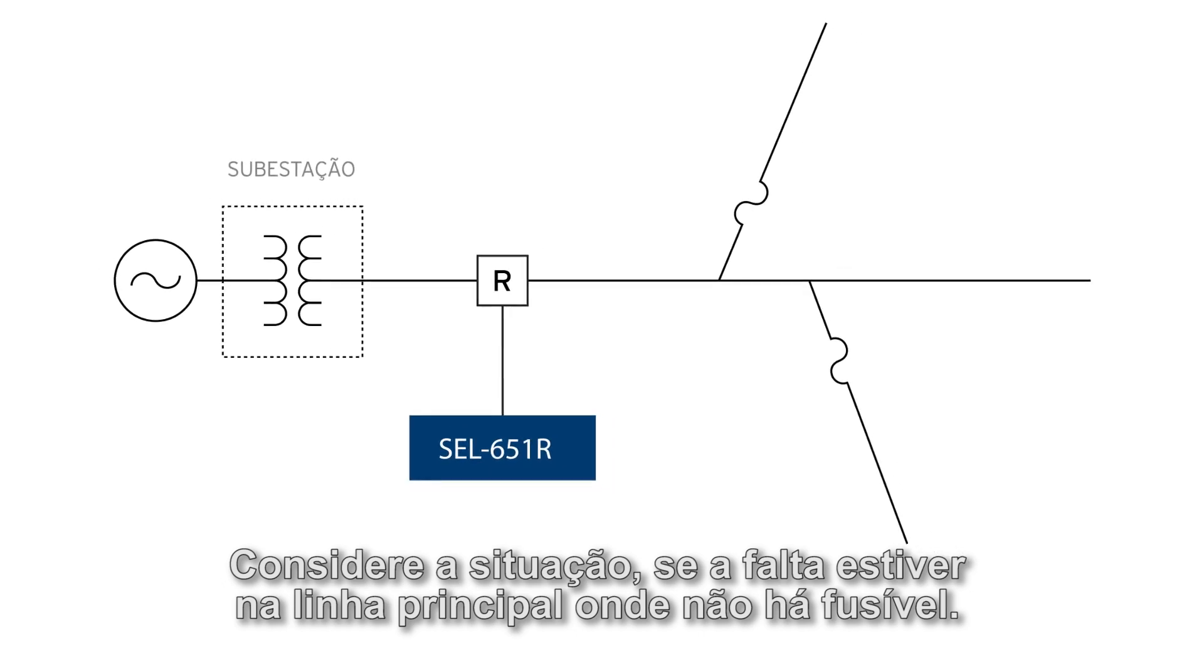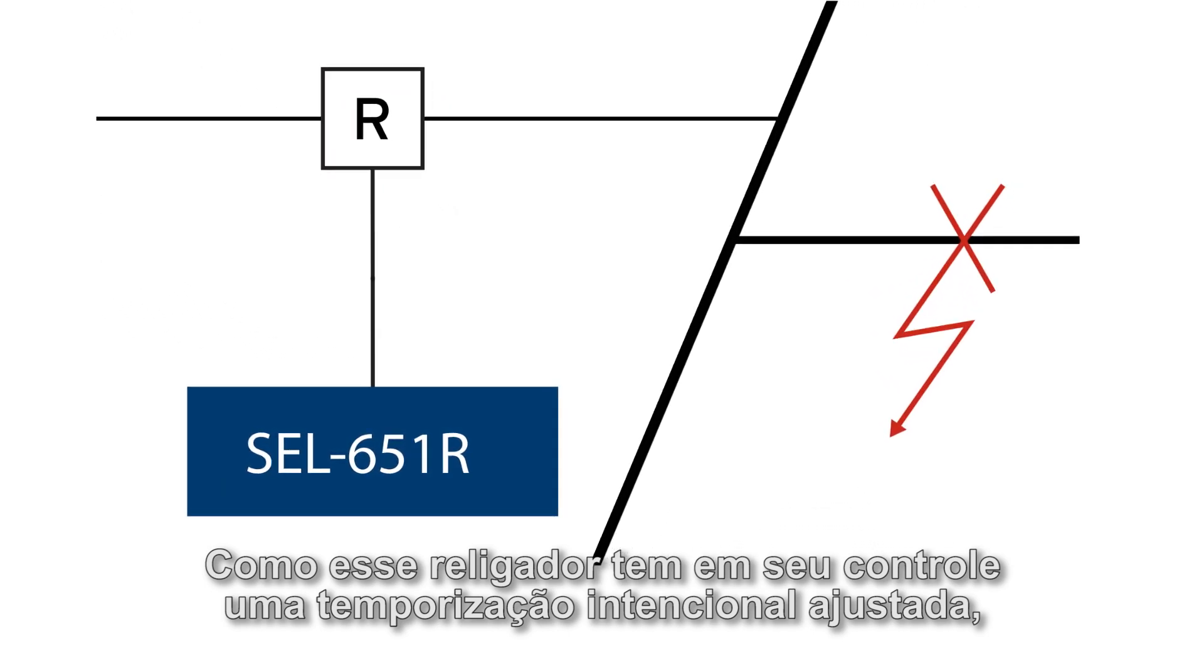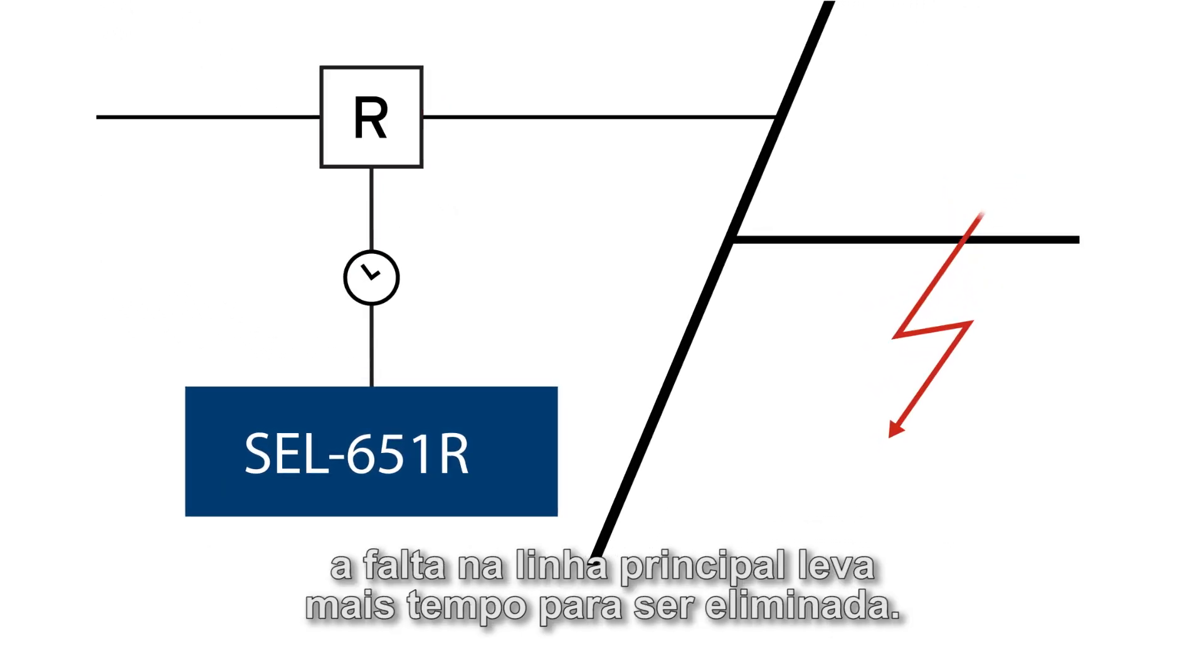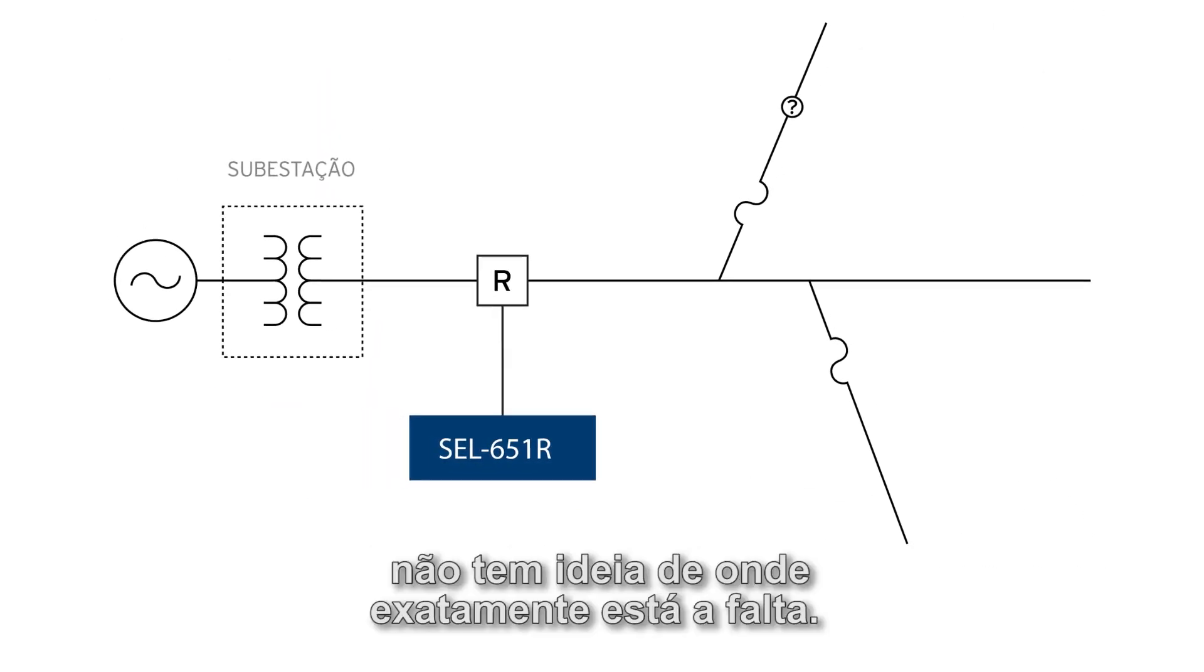Now consider the situation if the fault is on the mainline where there's no fuse. Because this recloser and the recloser control have built-in delay, the fault on the mainline takes longer time to clear. This is due to the fact that the recloser control has no idea where exactly the fault is.